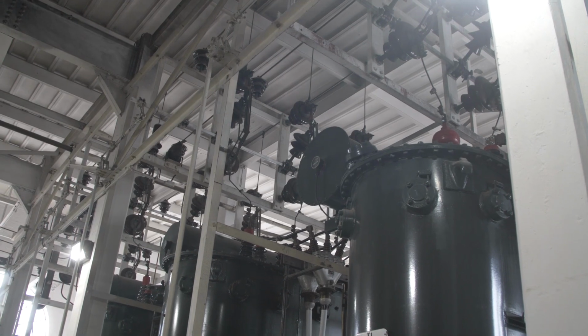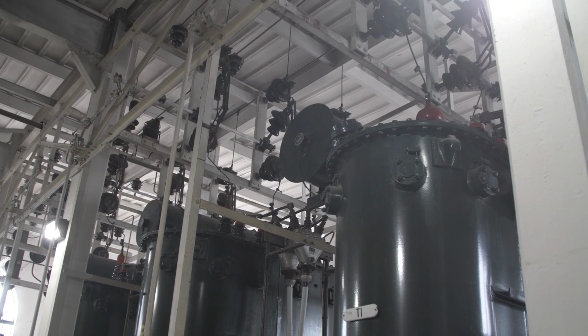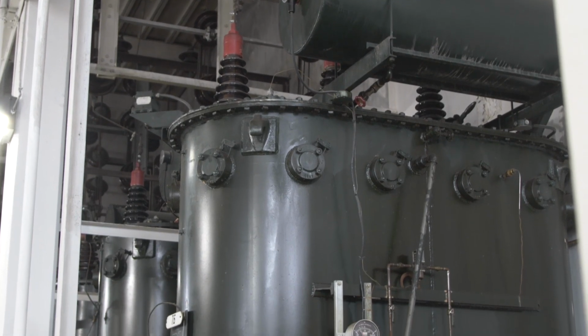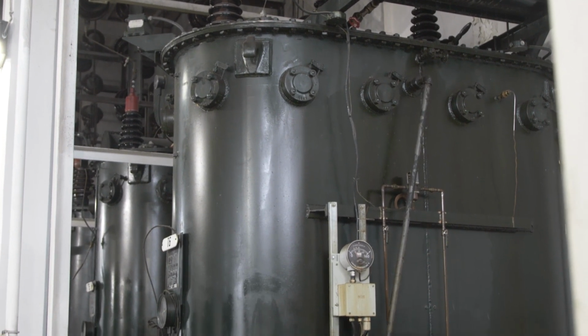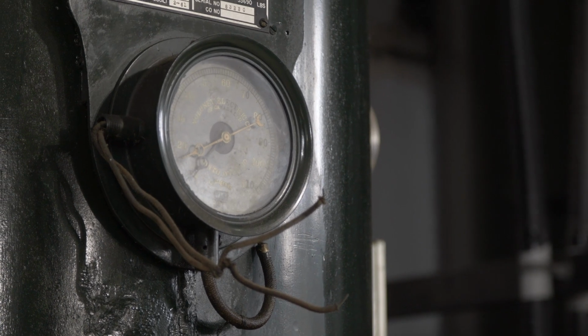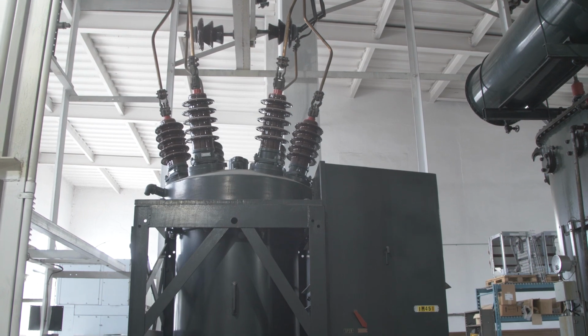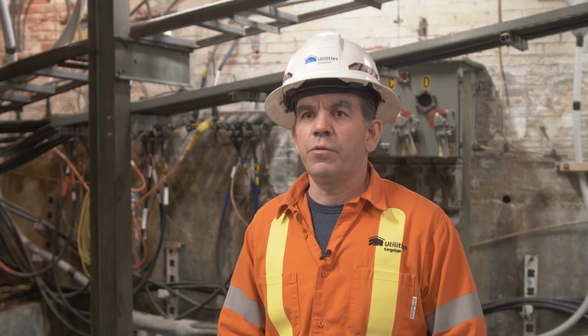We have six 3 MVA transformers from the 1930s, so we do oil tests twice a year, and the oils are showing there's trouble inside, so we have to look to replace those. We also have three oil circuit breakers of the same vintage, which we're going to replace with modern devices.